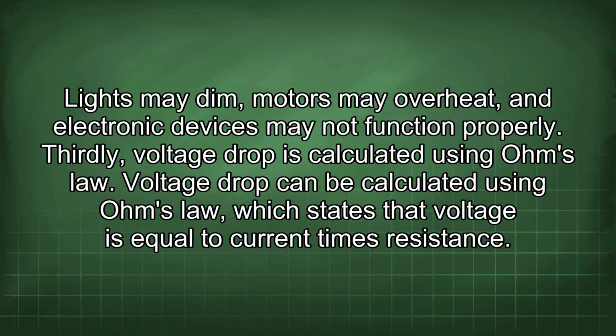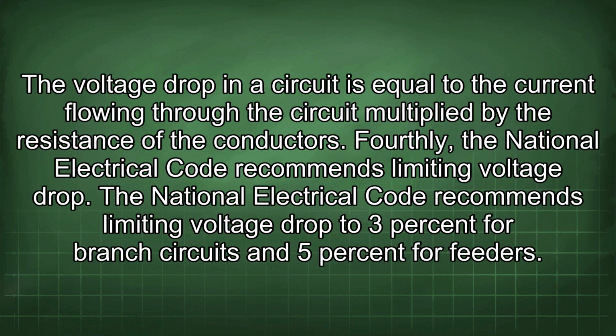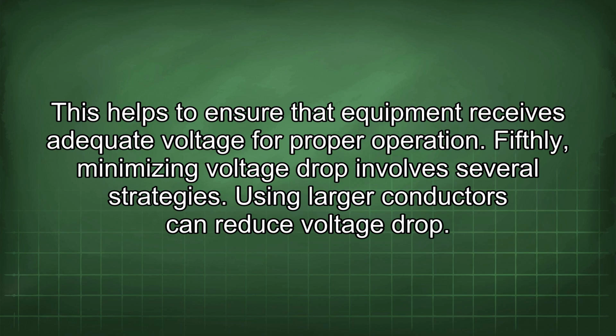Thirdly, voltage drop is calculated using Ohm's law. Voltage drop can be calculated using Ohm's law, which states that voltage is equal to current times resistance. The voltage drop in a circuit is equal to the current flowing through the circuit multiplied by the resistance of the conductors. Fourthly, the National Electrical Code recommends limiting voltage drop. The National Electrical Code recommends limiting voltage drop to 3% for branch circuits and 5% for feeders. This helps to ensure that equipment receives adequate voltage for proper operation.